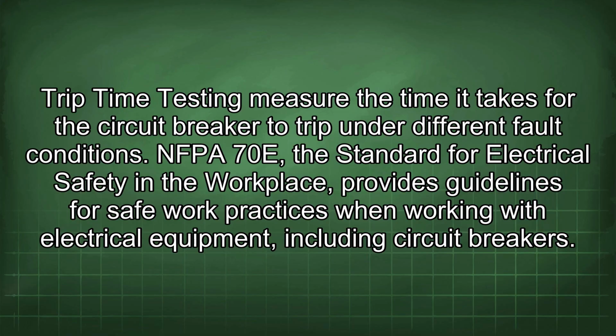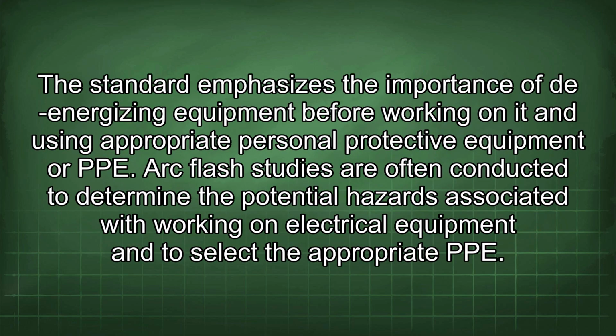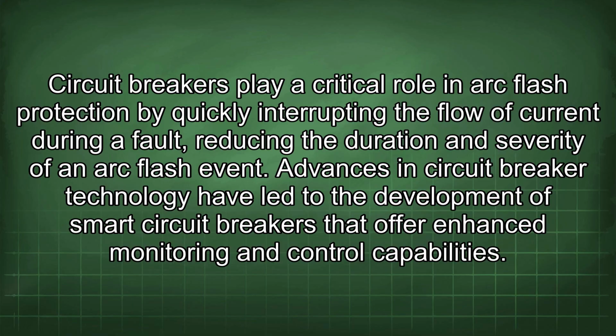NFPA 70E, the standard for electrical safety in the workplace, provides guidelines for safe work practices when working with electrical equipment, including circuit breakers. The standard emphasizes the importance of de-energizing equipment before working on it and using appropriate personal protective equipment, or PPE. Arc flash studies are often conducted to determine the potential hazards associated with working on electrical equipment and to select the appropriate PPE. Circuit breakers play a critical role in arc flash protection by quickly interrupting the flow of current during a fault, reducing the duration and severity of an arc flash event.